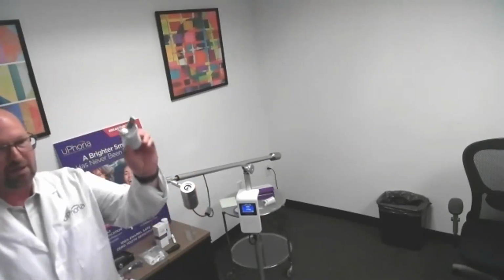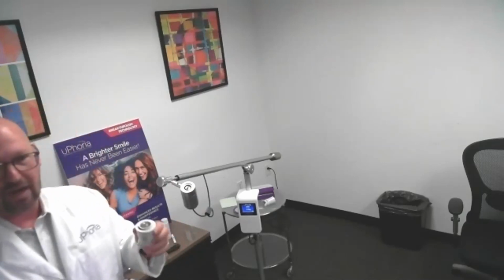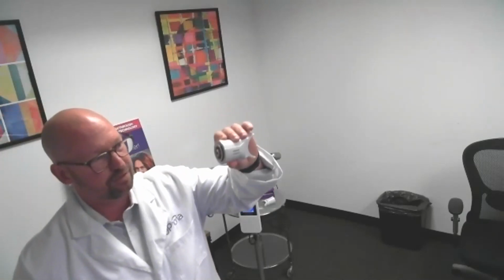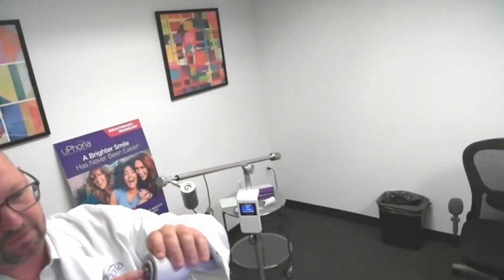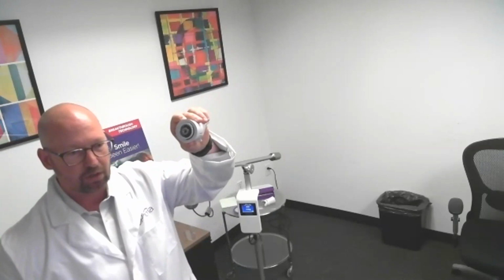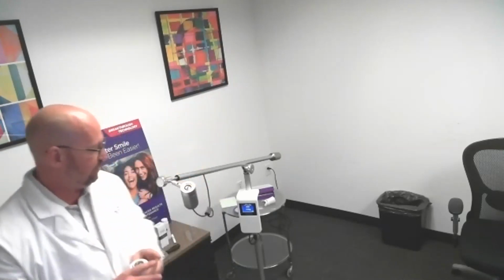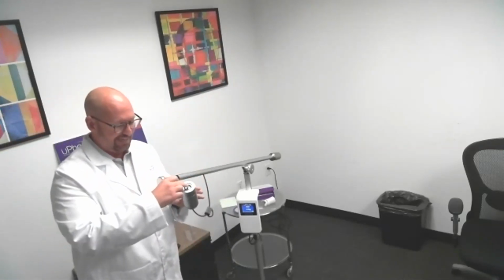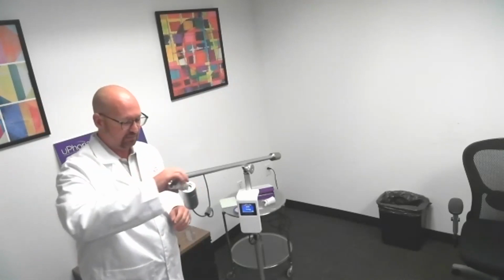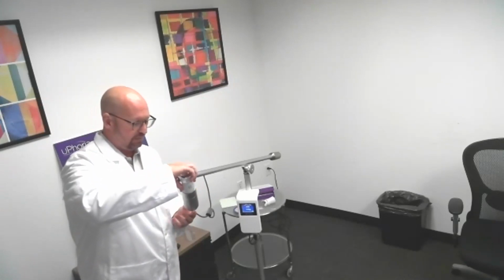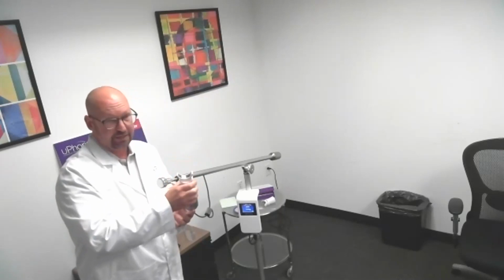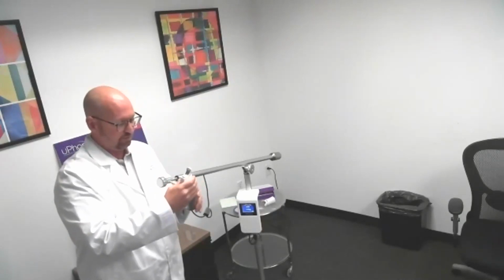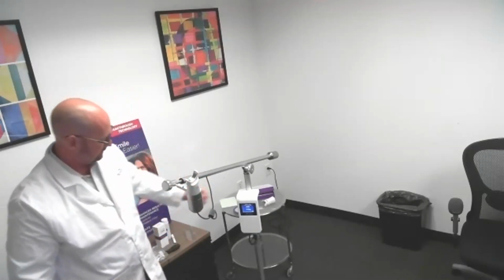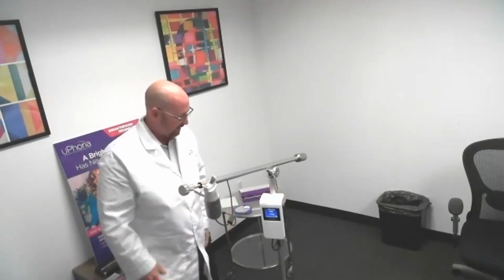So when you put the mouthpiece on, after you do a treatment, you want to make sure there's a smooth metal finish on it. Sometimes there's a little buildup from the autoclave machine or whatnot, and you want to wipe that down, because you want complete contact with the ultrasonic unit and this metal piece. If you don't, the system will error out and you won't have any cavitation. So you just simply screw it on. You don't have to over tighten it, but you'll know it's completely applied once you tighten that.